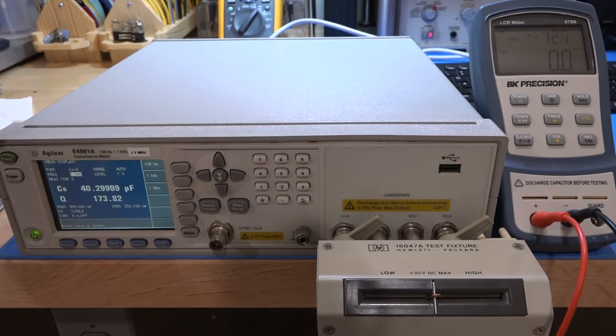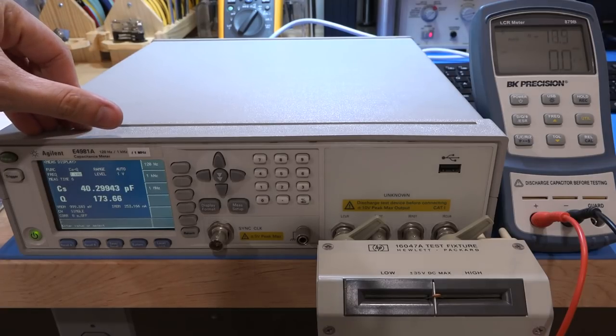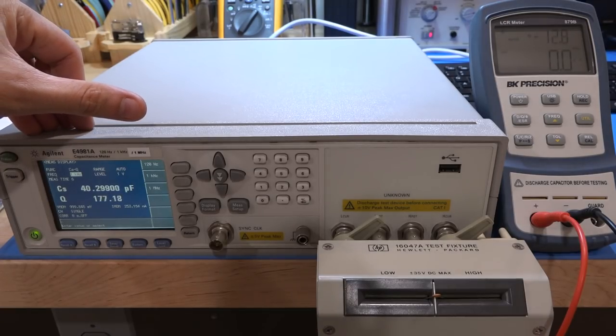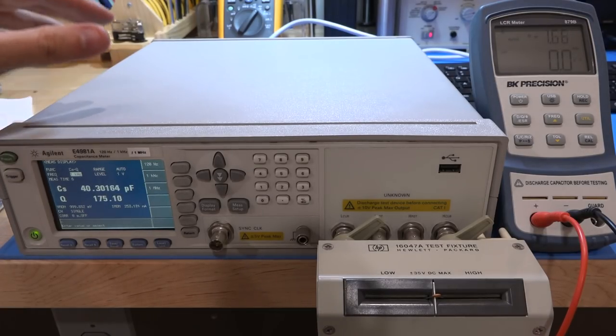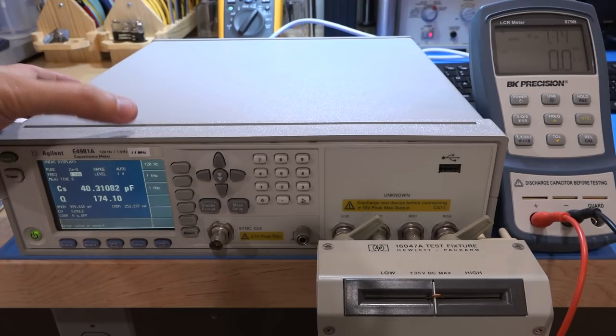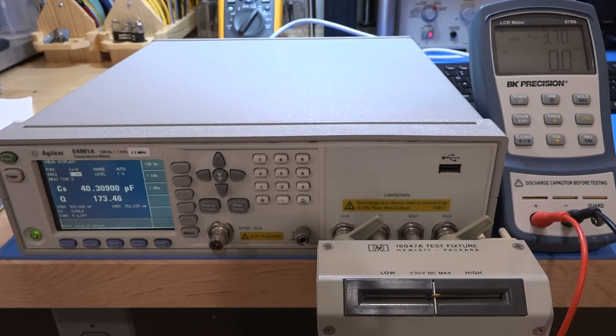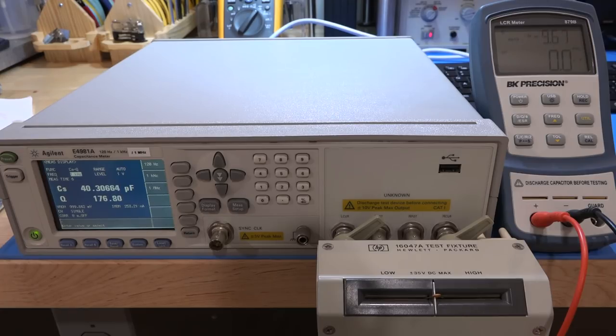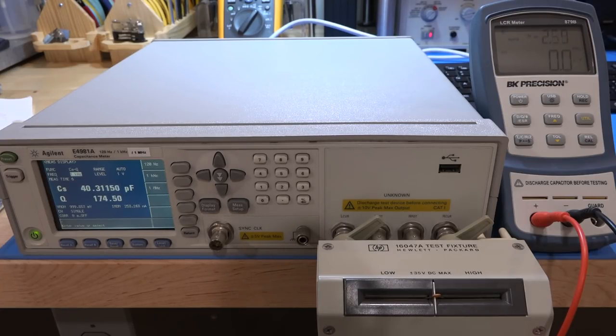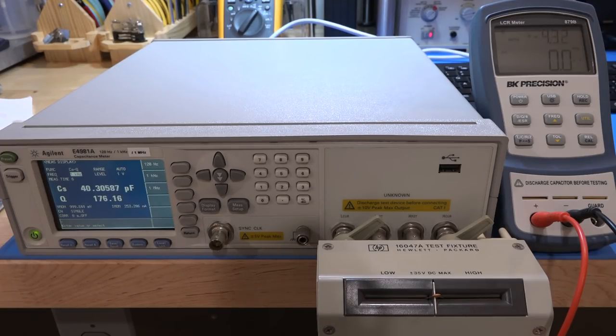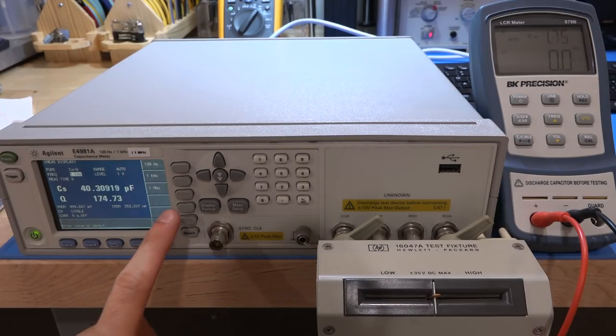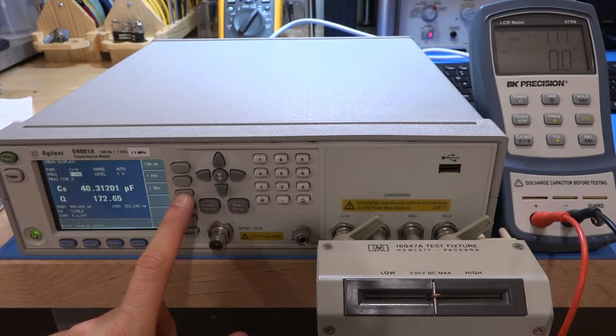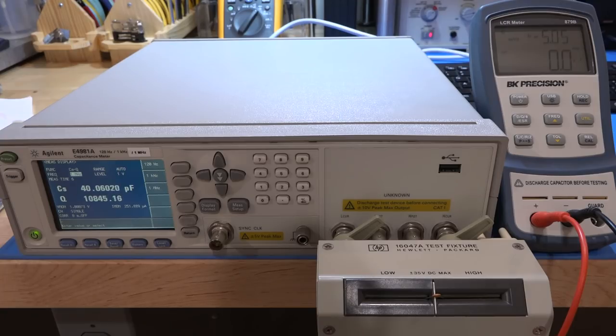Now let's take this capacitor out. Let's put it into our test fixture and let's see what the capacitance meter actually says. Here we go. And check it out. It's pretty close. We got a capacitance measurement of 40.2 picofarad, which is almost exactly what the other one was saying. Quality factor was 168. It is going up a little bit, maybe because it's cooling down after I was handling it in my hand. But yeah, it's kind of stabilizing now. The measurement makes sense. Now, this particular unit has 120 hertz, 1 kilohertz, and 1 megahertz measurement options. So this is option 001, which gives you 1 megahertz, which is actually quite expensive. I think it would be several thousand dollars just to get this 1 megahertz measurement.